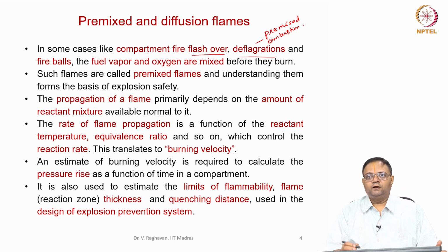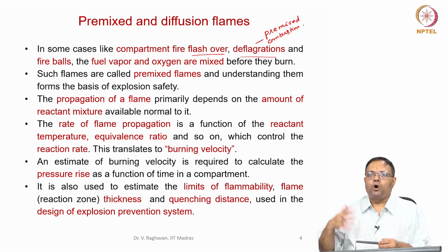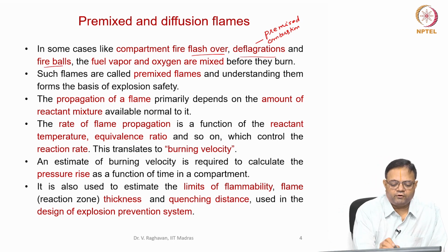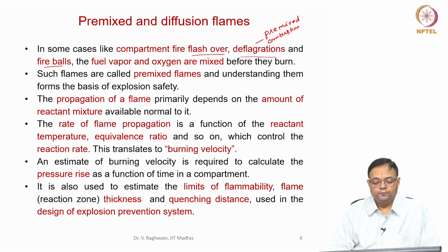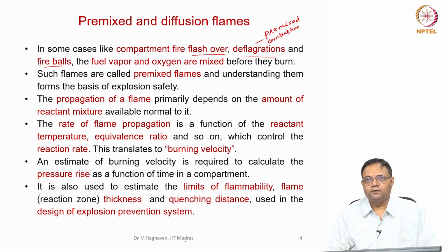Similarly, when the premixed reactants can open a vent and go out, they can form fireballs. So, we can see that a compartment fire, which is primarily a non-premixed fire, can start, flashover can occur, or deflagration can be initiated, and fireballs can also result.